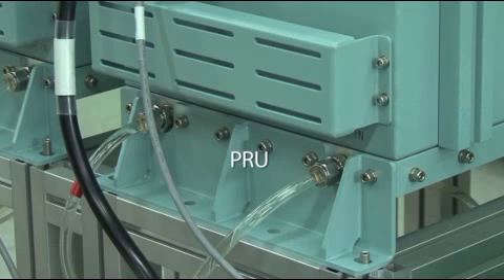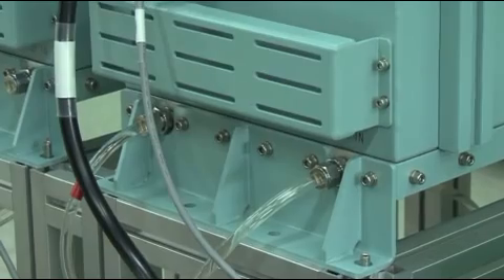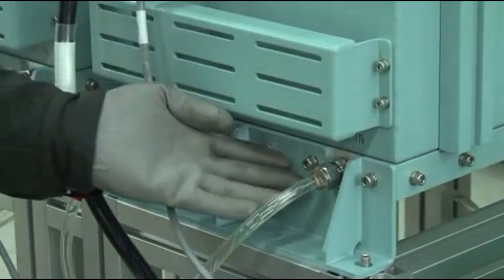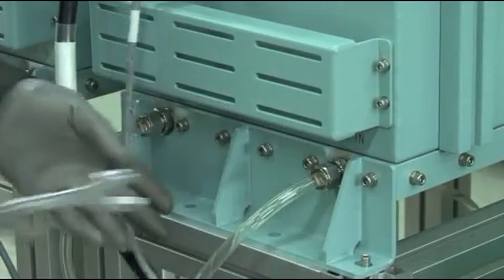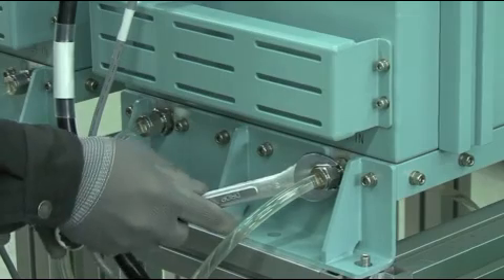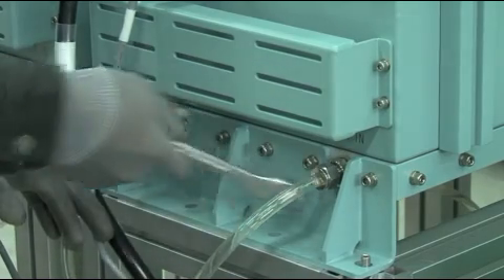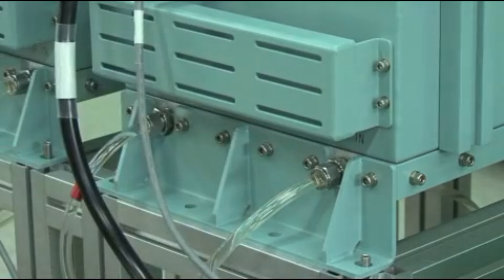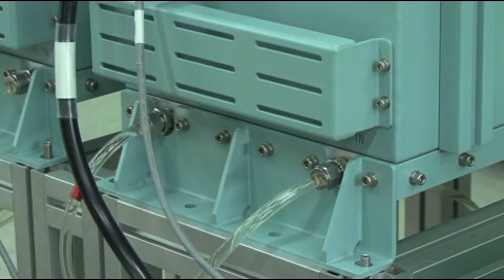3. PRU. 3-1. Checking leakage of cooling water connector. Step 1. Check leakage from both inlet and outlet cooling water connector. Step 2. Tighten the connector using tools in case of leakage. Step 3. Reassemble the connector if the leakage continues.